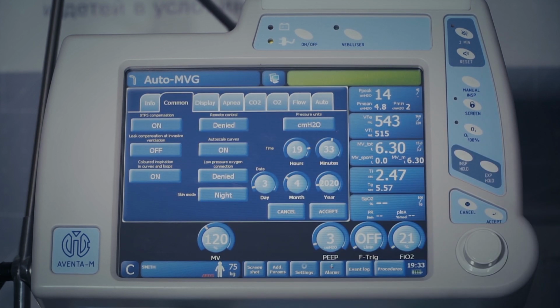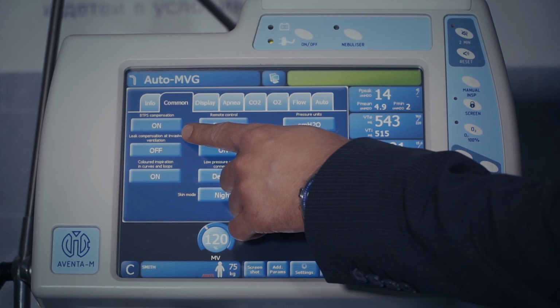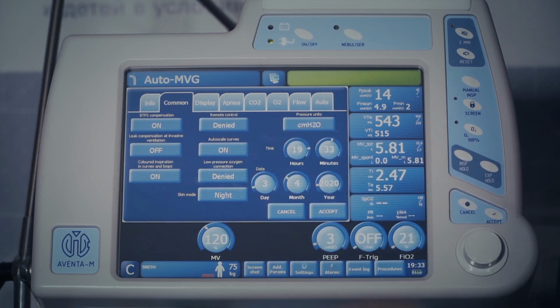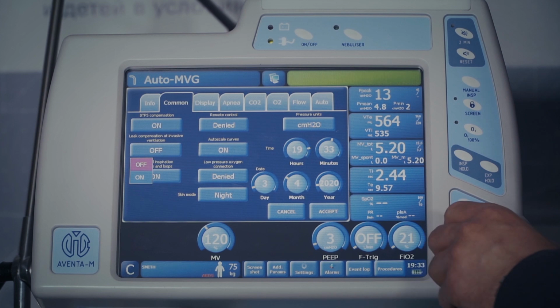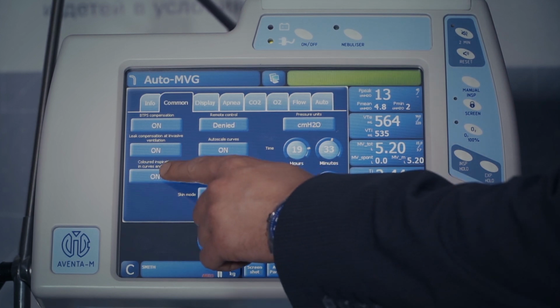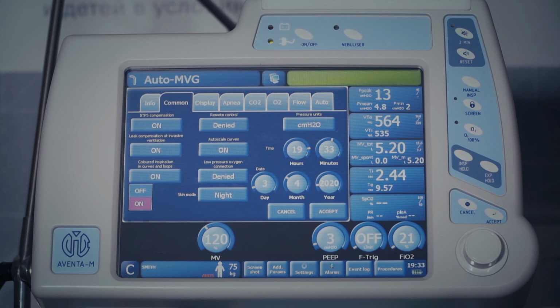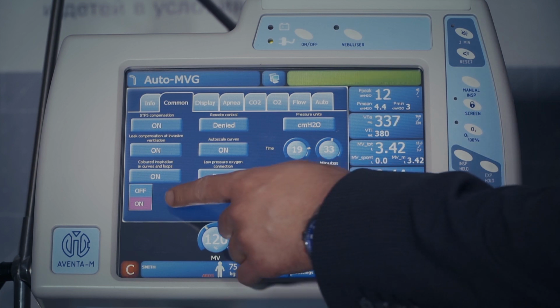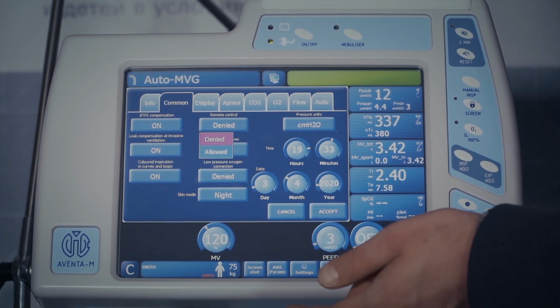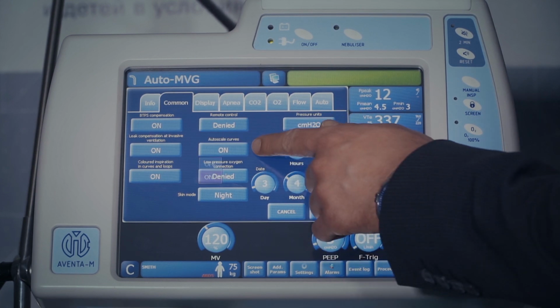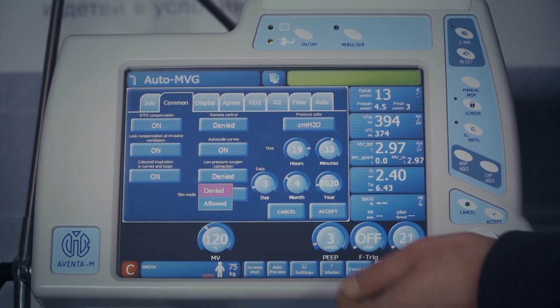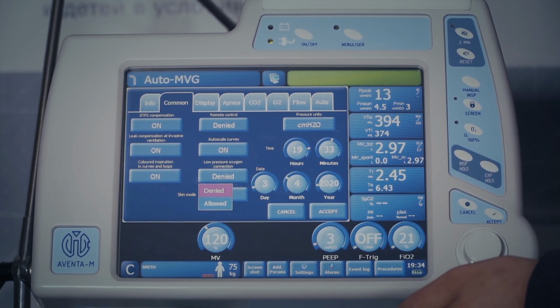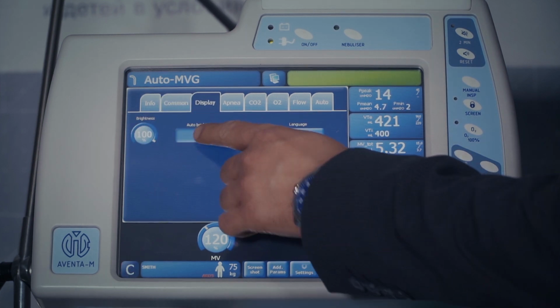In the second tab, Common, it is possible to adjust the ventilator system time, temperature, and humidity compensation, compensation of leakage in the breathing circuit, auto-scaling of curves and loops. If lung ventilator is used together with a low-pressure oxygen concentrator, it is necessary to allow usage of low-pressure oxygen. Here, it is also possible to change the color of the displayed breathing curves depending on the respiratory phase and night and day color theme of the main screen. In tab Display, it is possible to adjust the run screen brightness.